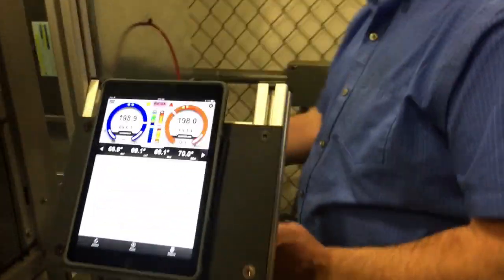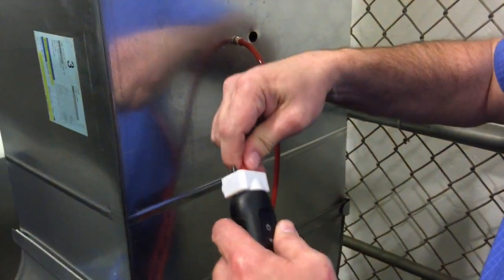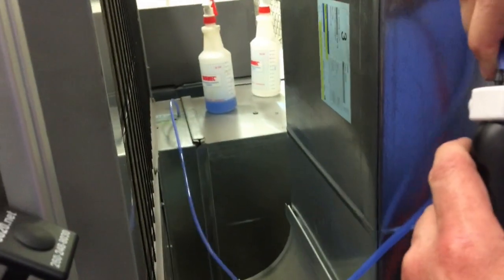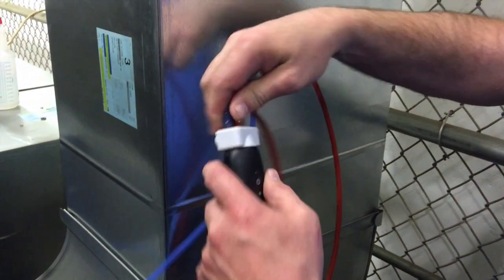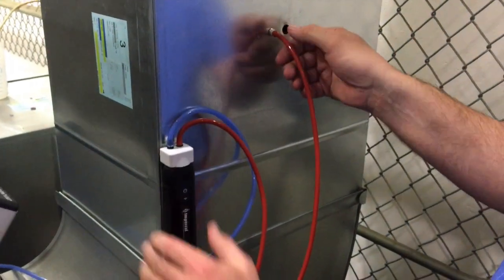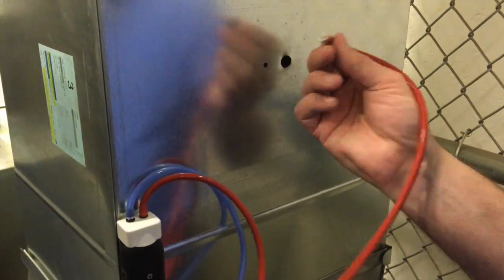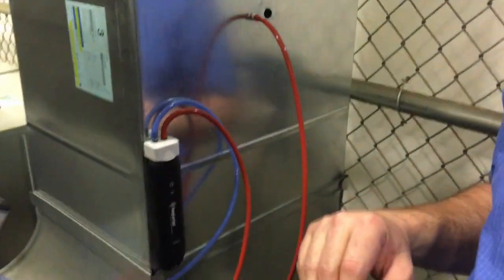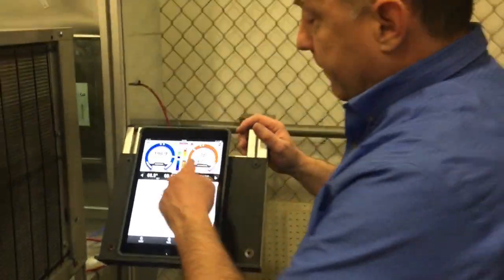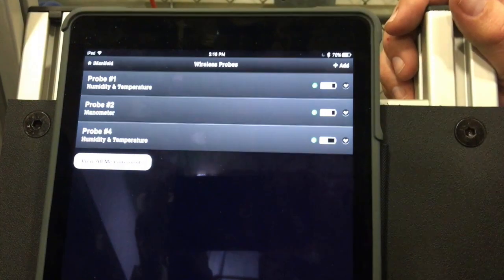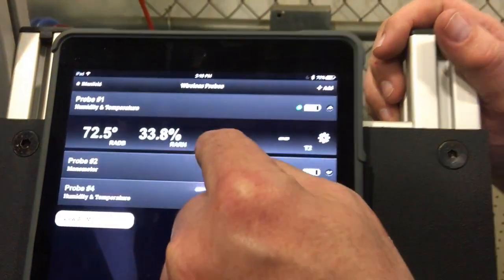The next step is to hook up our manometer. So I'm going to go ahead and connect my supply and my return. These are magnetic static pressure tips here. So these just simply attach into the duct with a magnet. They're what they call flush mount tips. So there's just a very small amount that penetrates into the ductwork, and that's all there is to hooking up the manometer. Now I'm going to go back here. I'm going to just check my wireless probes, make sure that all my probes are communicating, and now we're pretty well ready to go.